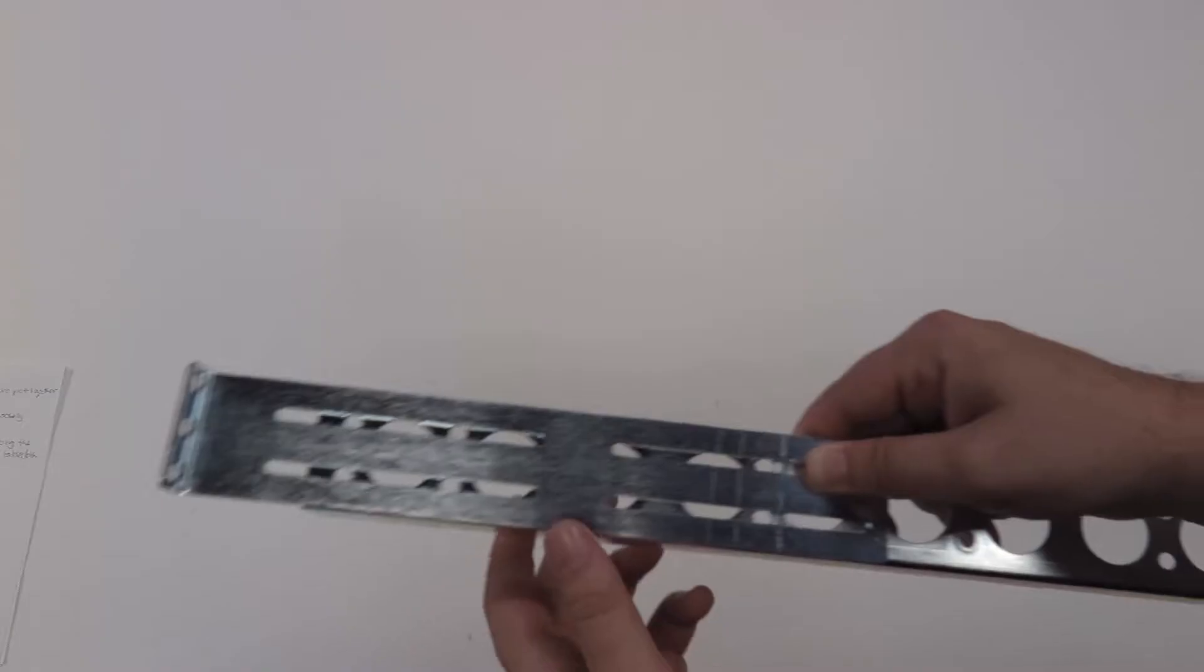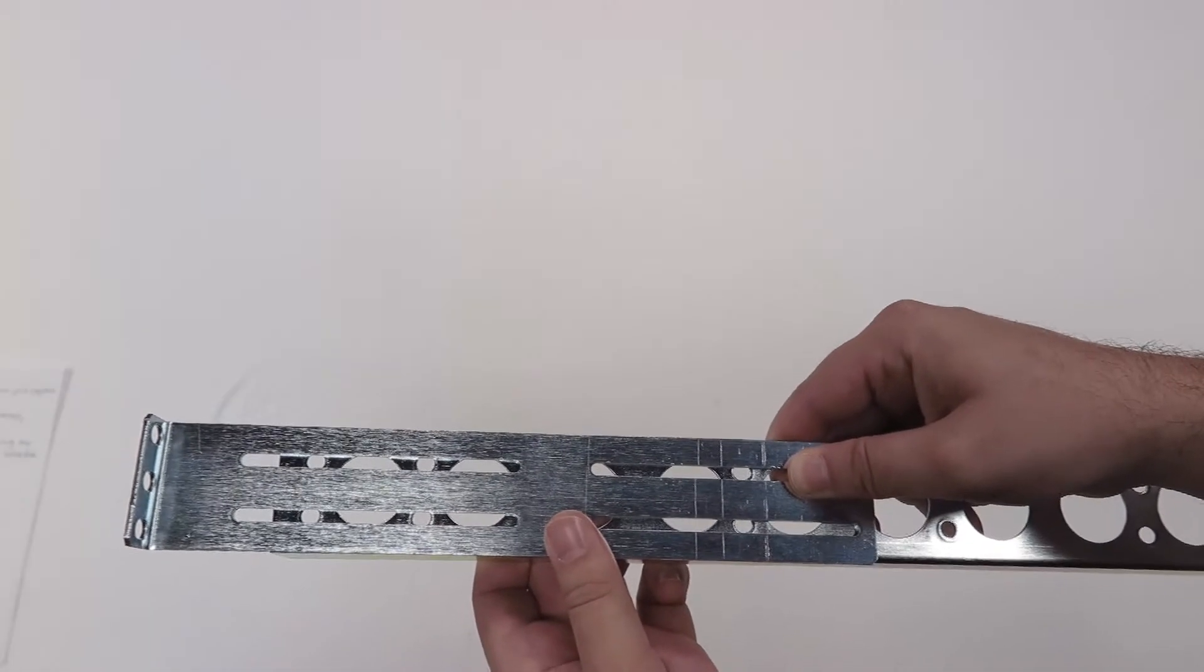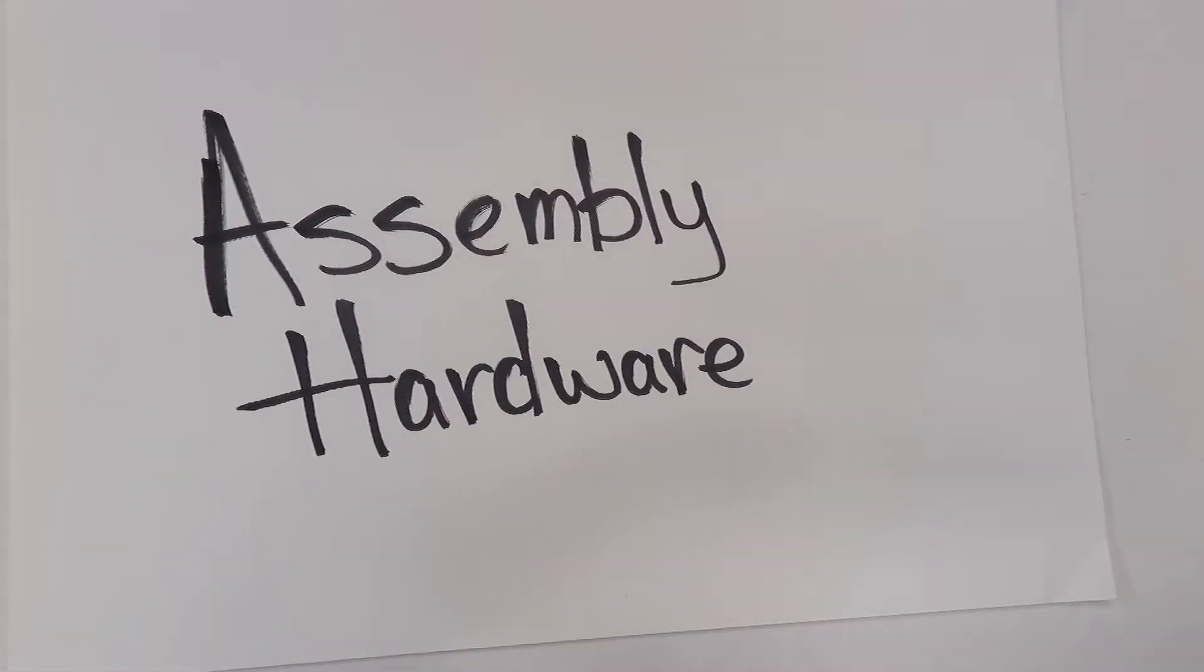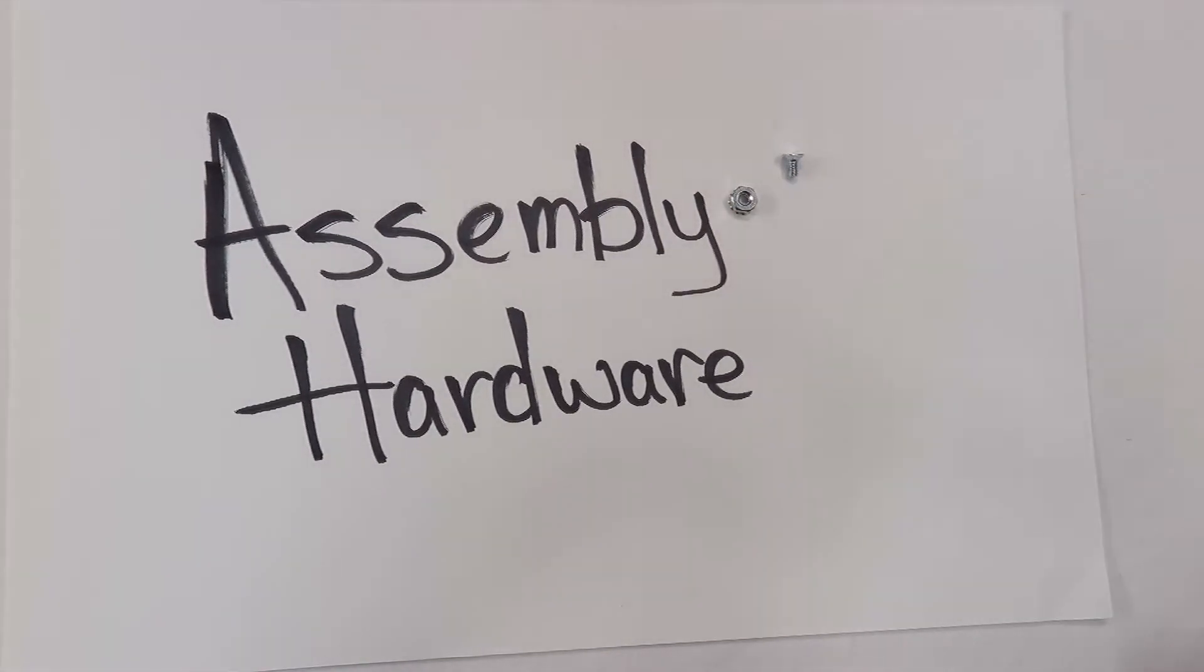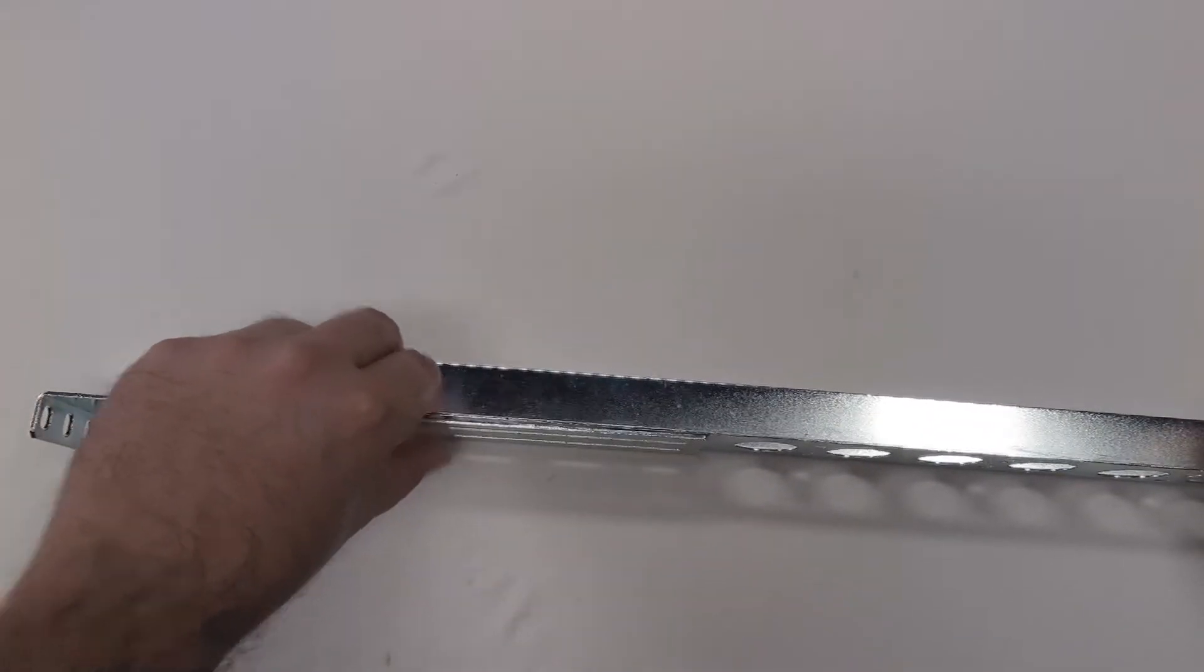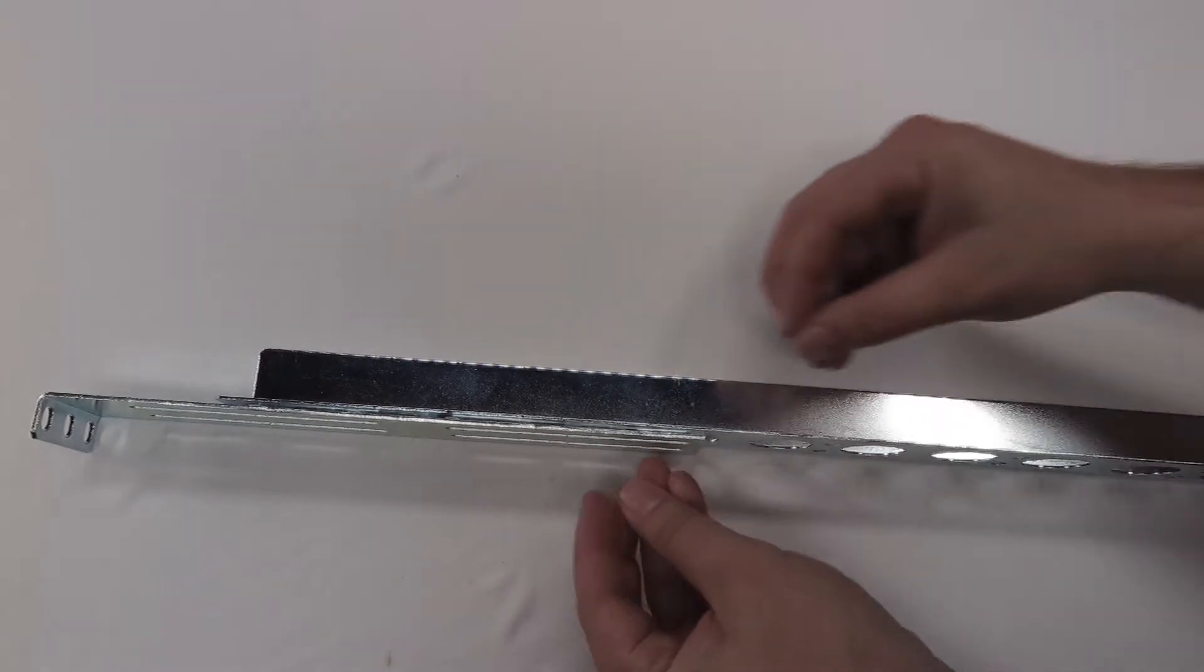This is how the rails attach. The part of the bracket that attaches to the rack is bent in the opposite direction as the lip that holds your server. Using the 8-32 flathead screws and 8-32 nuts, you can attach the rail and rear bracket. The flathead screws will enter through the rail while the nuts secure the screws from outside of the rear bracket.